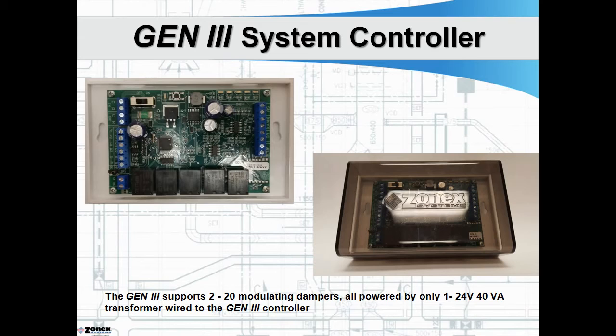The GenIII controller wires to the HVAC equipment and every minute communicates with each damper in the system via an RS-485 communications loop, evaluating heating and cooling calls for each zone. The controller then initiates control decisions for the unit based on our first call, first serve, majority wins on changeover algorithm.